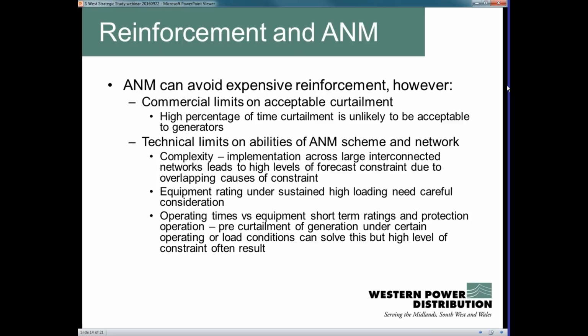We also have to be slightly careful about equipment ratings. Our equipment is rated in terms of the amount of current it can carry, based on the assumption that we'll see a cycling of load - it will go up and down during the day. However, with extensive use of active network management, we begin to flatten that load curve, filling in some of those troughs, so we have to be careful about the ratings we use on the assets in those circumstances.